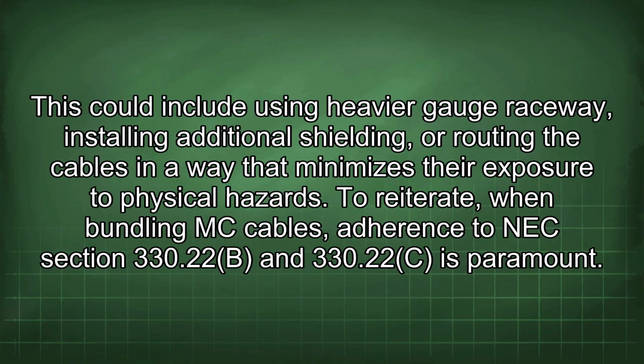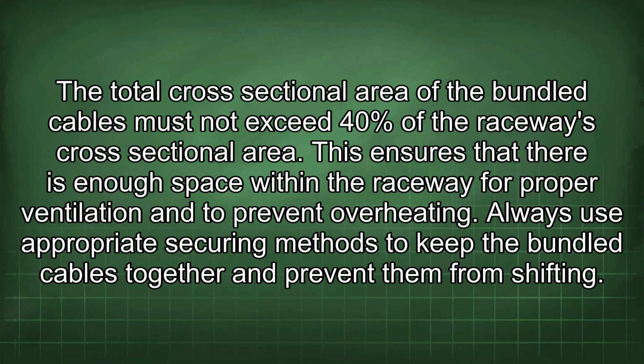This could include using heavier gauge raceway, installing additional shielding, or routing the cables in a way that minimizes their exposure to physical hazards. To reiterate, when bundling MC cables, adherence to NEC Section 330.22b and 330.22c is paramount. The total cross-sectional area of the bundled cables must not exceed 40% of the raceway's cross-sectional area. This ensures that there is enough space within the raceway for proper ventilation and to prevent overheating.